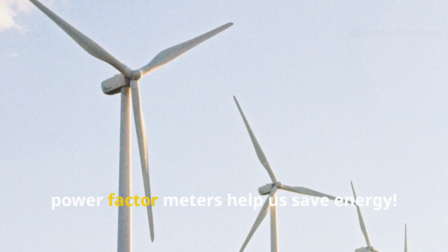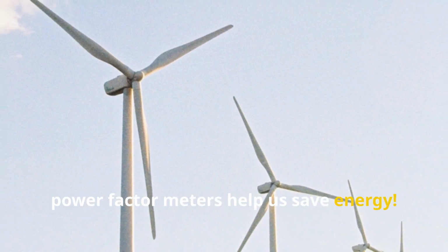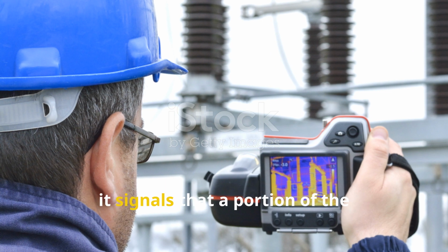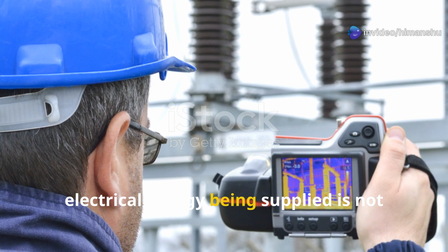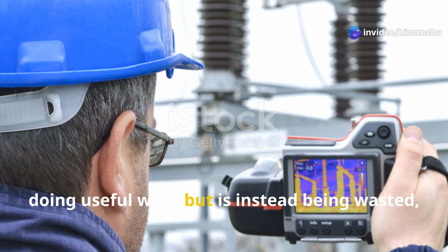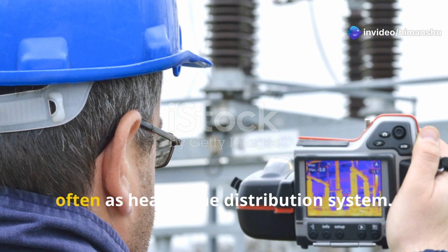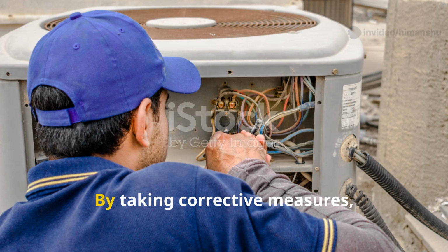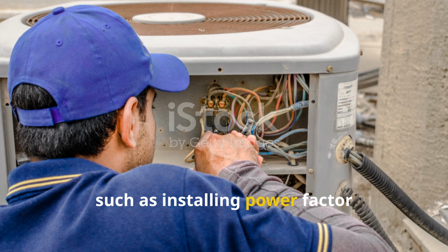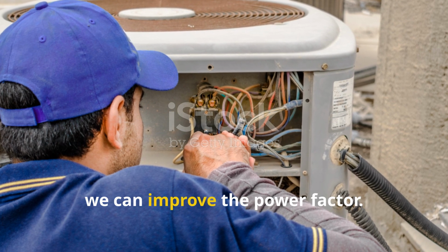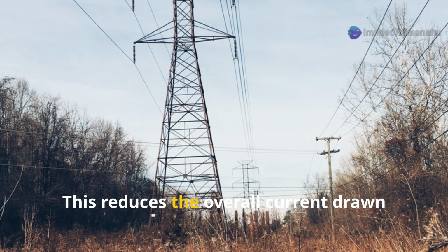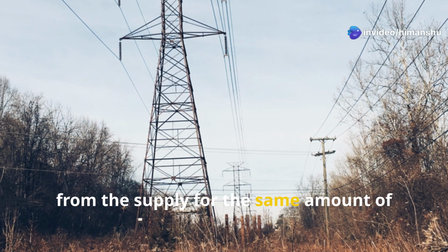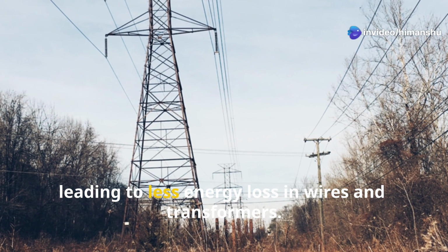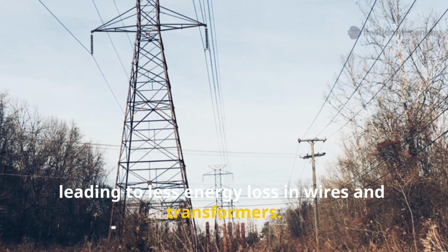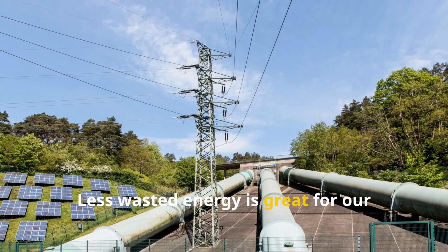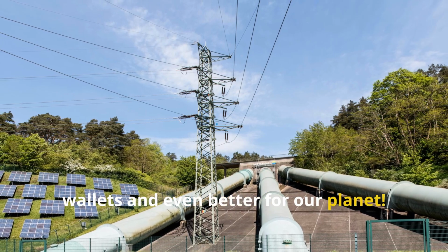First and foremost, power factor meters help us save energy. When we identify a low power factor, it signals that a portion of the electrical energy being supplied is not doing useful work, but is instead being wasted, often as heat in the distribution system. By taking corrective measures, such as installing power factor correction capacitors, we can improve the power factor. This reduces the overall current drawn from the supply for the same amount of useful work, leading to less energy loss in wires and transformers. Less wasted energy is great for our wallets and even better for our planet.